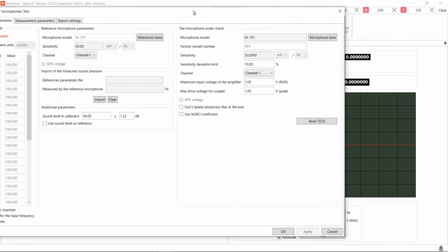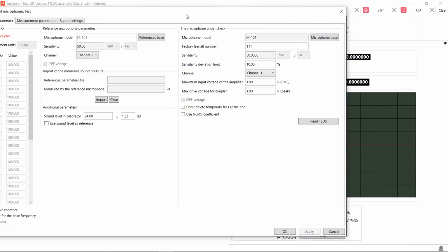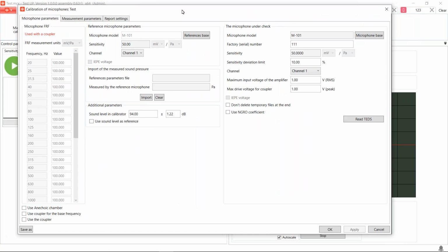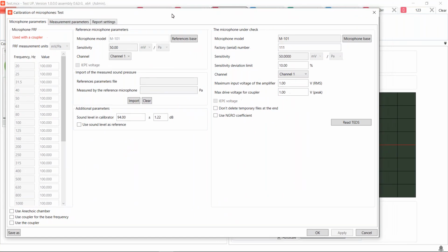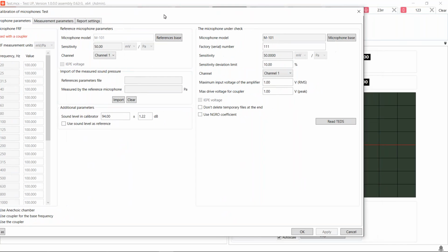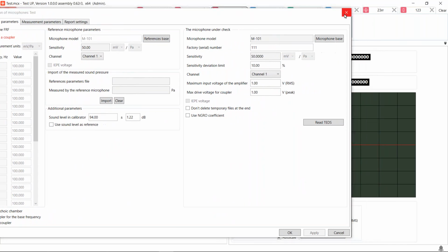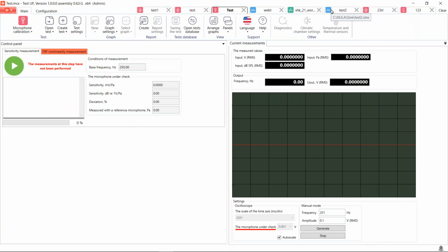Next, you are to specify the parameters of the microphone under check. So you are to enter here the serial number of the microphone, its sensitivity, sensitivity deviation limit, channel, and so on. And after the calibration procedure is done, of course, you will get your report automatically. And finally, we would like to give you a sneak peek at the upcoming module of sound level meters calibration.